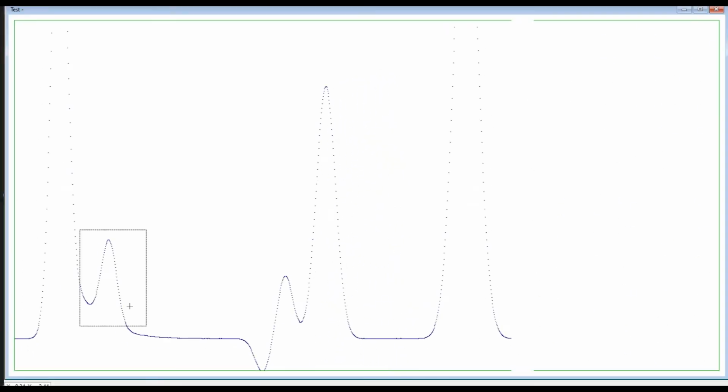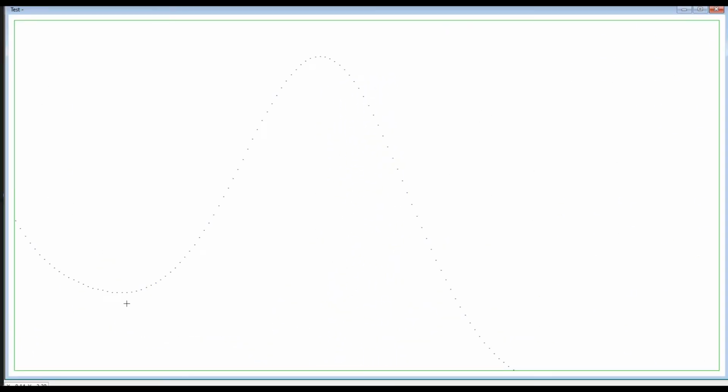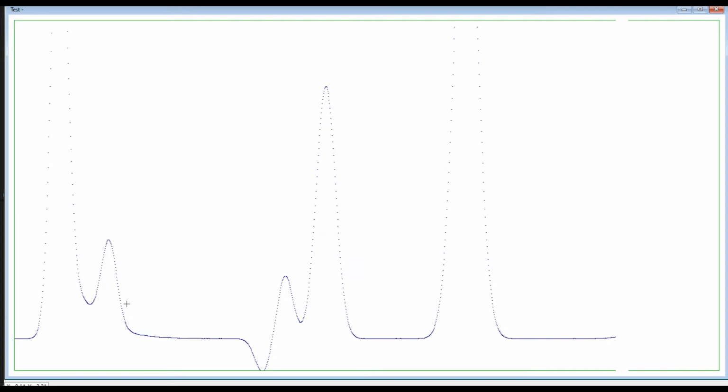Therefore, the digitized record does not contain all of the information in the original detector signal. Information is invariably lost during the process of digitization. Fortunately, we do not need all of the information in the detector signal. Information theory will tell us how to get sufficient information for our purposes. There are only two issues. The sample rate must be fast enough to catch all meaningful changes in the signal. The amplitude must be measured precisely enough to see the smallest meaningful variation in the signal.